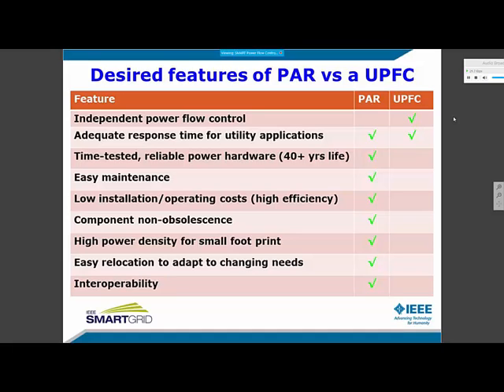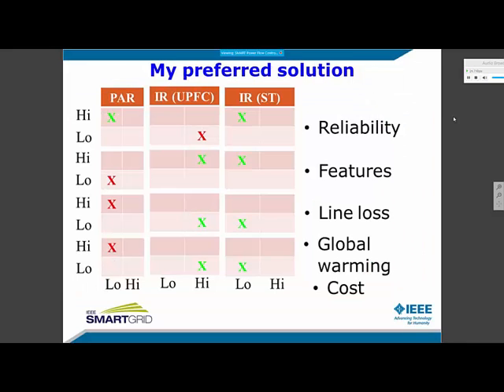In addition, the PAR offers time-tested, reliable power hardware with 40-plus years of lifespan, easy maintenance, low installation and operating cost, high efficiency, component non-obsolescence, high power density for a small footprint, easy relocation to adapt to changing needs with the new generation and loads, and interoperability. This leads to my preferred solution as follows. Each metric, reliability, features, line loss, global warming, is checked as high or low, along with the cost of a solution as high or low.